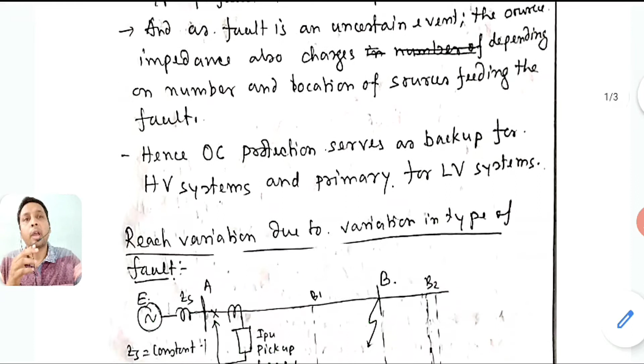So hence overcurrent protection is the backup for high voltage transmission lines or high voltage systems. It is not the primary protection for high voltage systems, but it is primary for low voltage systems due to cost. So for low voltage, it is still preferred as a primary protection, but for high voltage, that is in transmission lines, these overcurrent relays are used as a backup. The primary becomes your distance relay.